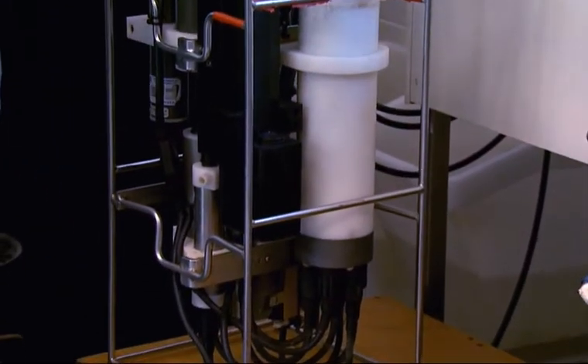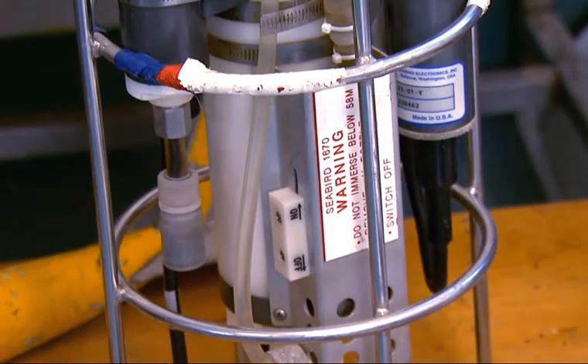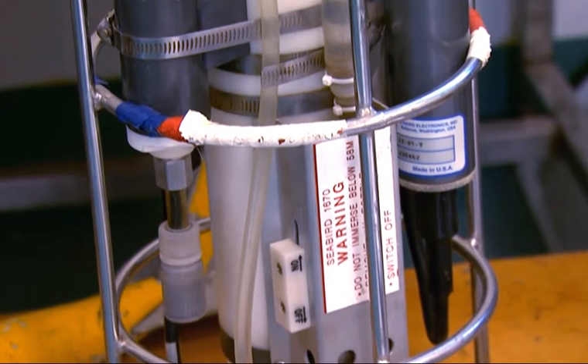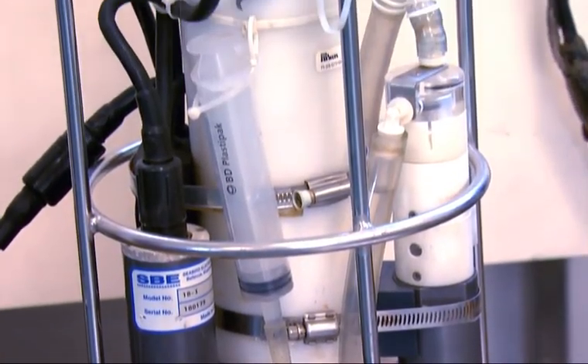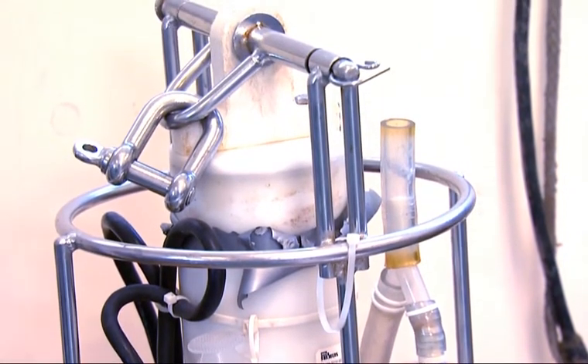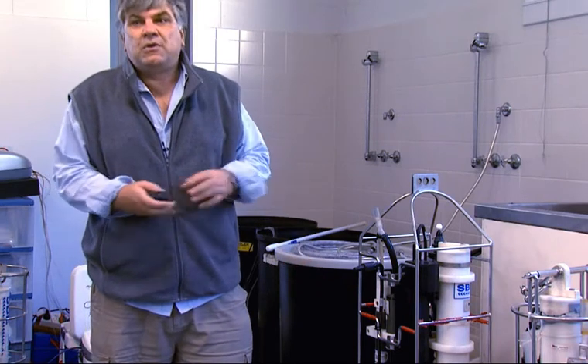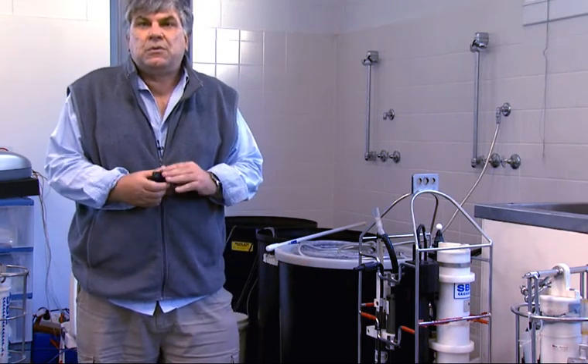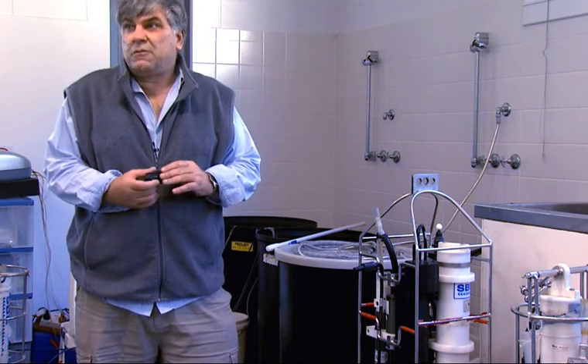The smaller instrument is basically a smaller version of this one, which collects data with a speed of 2 Hz. These instruments are factory calibrated, and the accuracy of temperature, for example, is up to the third decimal point, then 1/1000th of a degree.